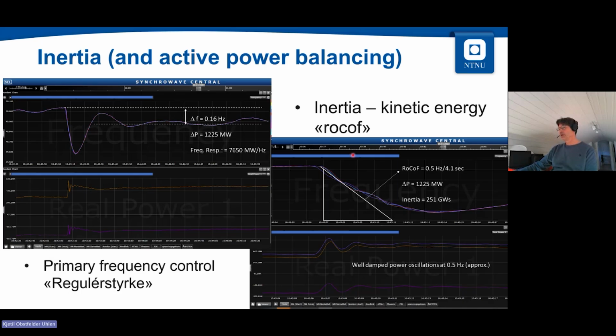We can also see something about the inertia or kinetic energy in the system, which is important to maintain the balance in the very short term. If we look at the rate of change of frequency, the ROCOF, we can estimate how much kinetic energy we have. In this case it was fairly good, about 250 gigawatt seconds.